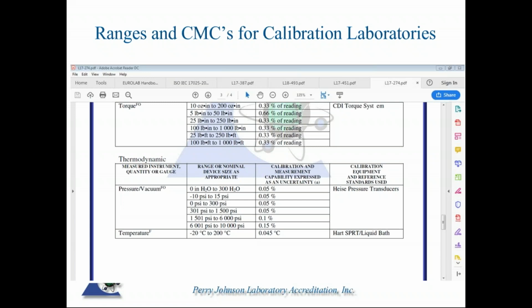Hence, they'll fulfill the requirement of being accredited to 17025. But if you look at the ranges, they're accredited to calibrate between those ranges, between minus 20 degrees C and 200 degrees C. Hence, if you had a need at 300 degrees C, this lab is not recognized under their accreditation to do so.